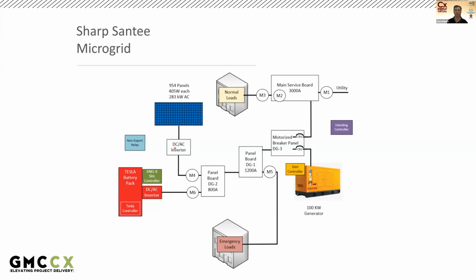These solar inverters are connected to an 800 amp panel board, which is this DG2 right here, which is also connected to the Tesla battery pack, which has a 140 kilowatt inverter and a 16 pod battery pack, which can store 225 kilowatt hours of electricity. The Tesla inverter is a grid forming inverter, which means it's responsible for creating and maintaining the voltage and frequency of the microgrid, and it ensures that excess power is tightly synchronized to the grid.